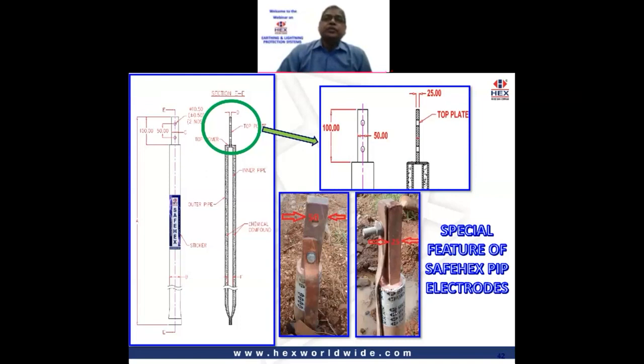Now, why have we kept this? Well, we all know that the current carrying capacity of any electrode depends on its cross-section area, isn't it? So if the cross-section area of both the inner and the outer pipe together is X, then the top plate must also match this area. Otherwise, it will create a bottleneck for the fault current to flow. A 76 mm OD by 3 meters long pipe in pipe has been successfully tested at CPRI for a fault current rating of 65 kiloamps for 1 second. Similarly, all our other pipe in pipe and earth rods have been successfully tested at CPRI.